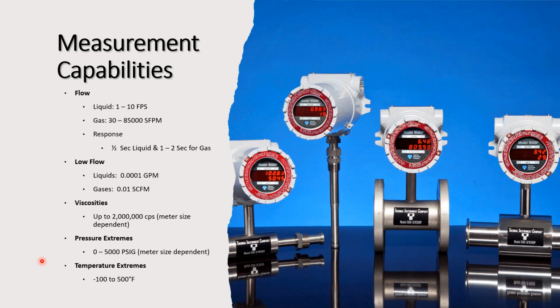And then temperatures, as you can see, anywhere from -100 degrees to 500 F. We typically cap our calibrations at 500 degrees F just because we don't have the capability to go much above that at our facility here in the Philadelphia area. But if you've got an application that's maybe a little bit above that, let's talk. We might be able to do something to help you out there. And all these numbers are really application dependent, but I just wanted to give you a nice general idea.